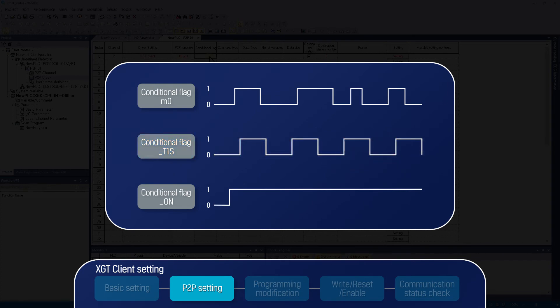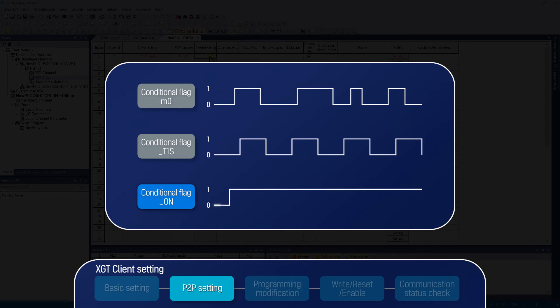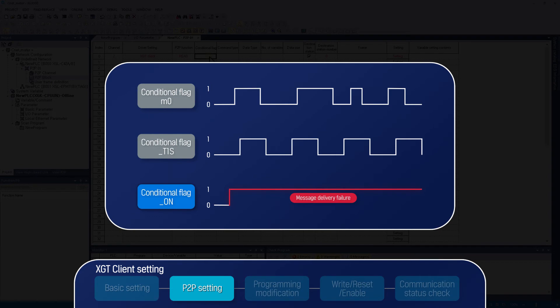As mentioned before, you could use system flags to trigger communication, but F99 bit device in XGK is not a proper conditional flag, as it is always on bit and does not change from 0 to 1.